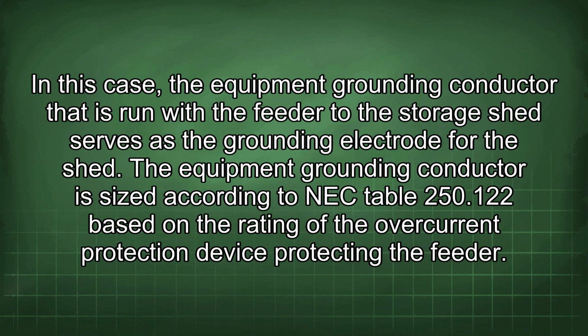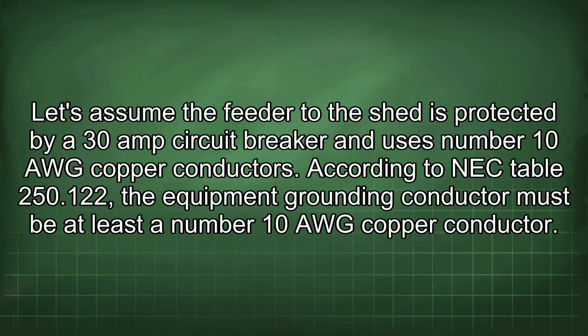In this case, the equipment grounding conductor that is run with the feeder to the storage shed serves as the grounding electrode for the shed. The equipment grounding conductor is sized according to NEC Table 250.122 based on the rating of the overcurrent protection device protecting the feeder. Let's assume the feeder to the shed is protected by a 30 amp circuit breaker and uses number 10 AWG copper conductors. According to NEC Table 250.122, the equipment grounding conductor must be at least a number 10 AWG copper conductor.